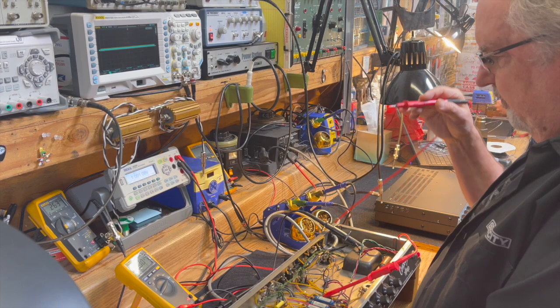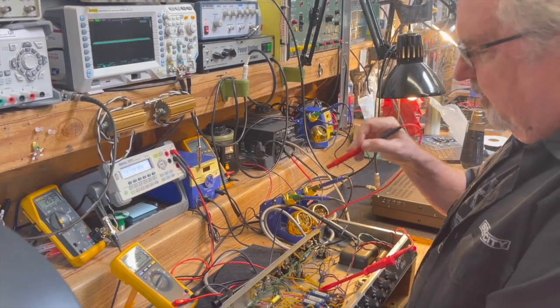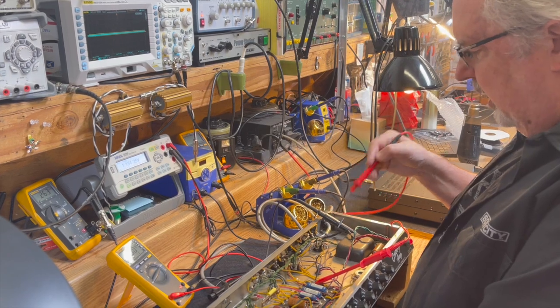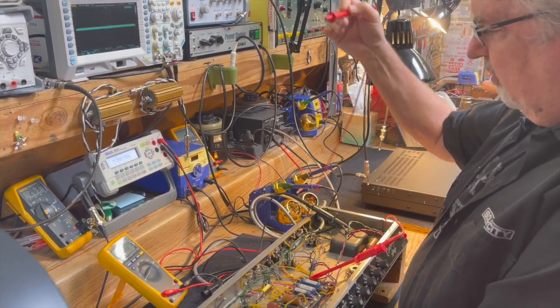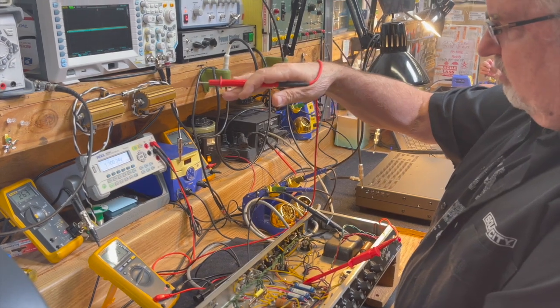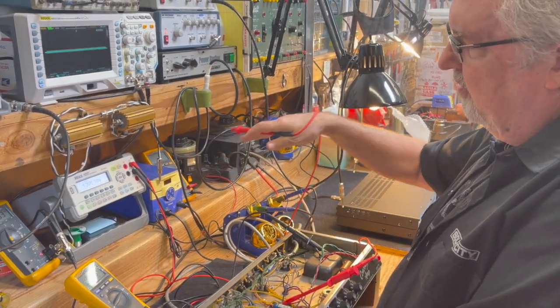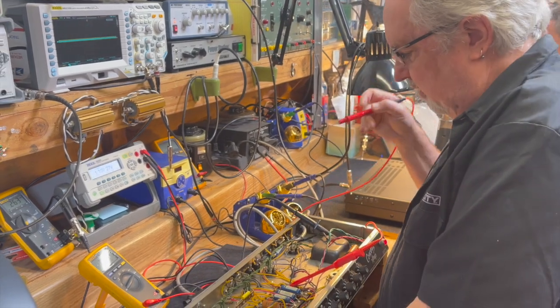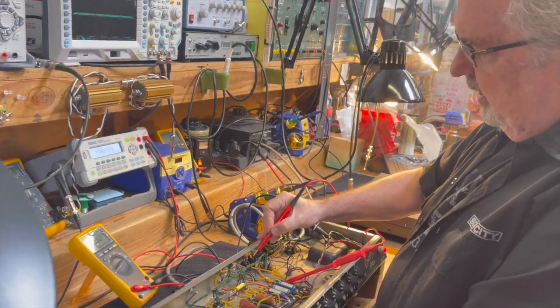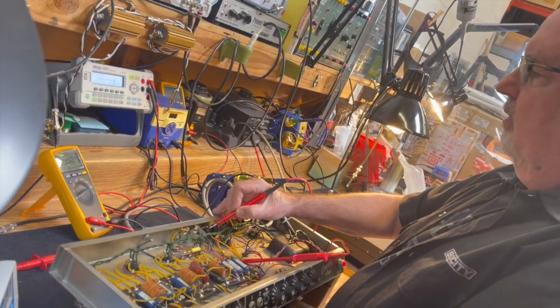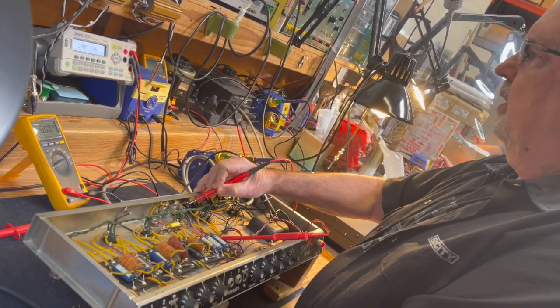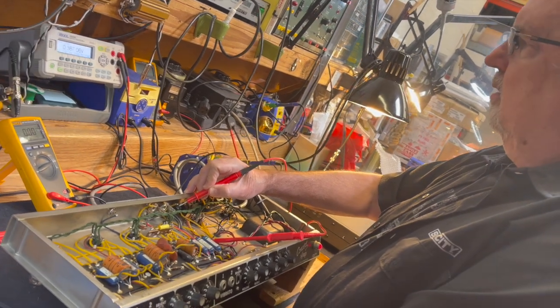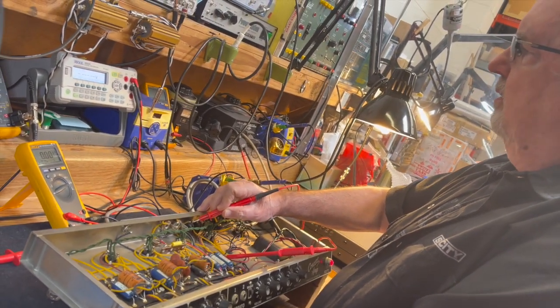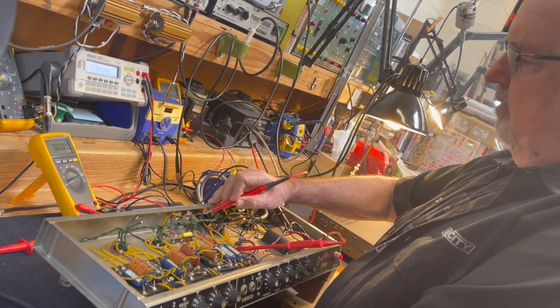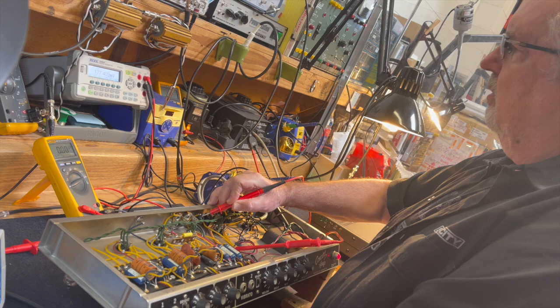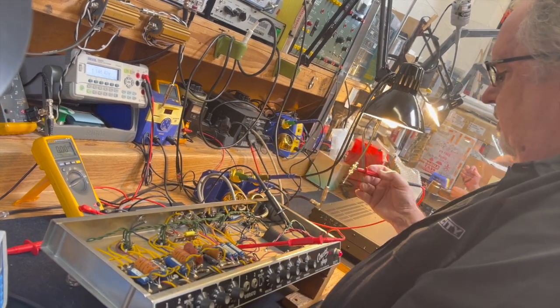You basically pump those 120 hertz humps into the filter caps, and the time it takes the filter caps to charge and discharge determines how much you smooth off the top of the humps in the rectification process. Normally in a solid state rectified power supply, you'll see roughly half a volt to a volt RMS of power supply ripple, because that's where all the current is being drawn from.